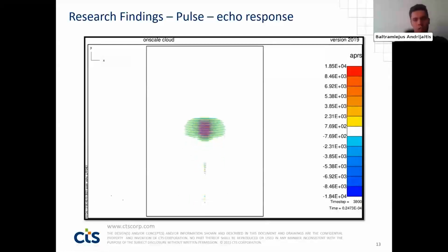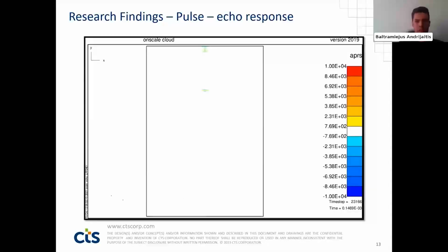This is the video pulse echo simulation. We can see high frequency 20 pulses that were excited in the ceramics, traveling in the water, hitting the mirror, and traveling back where the echo signal is read. So here, talking about what is important to perform a good pulse echo finite analysis. It is important to ensure that a high acoustic impedance material is used for the mirror. In this case, it was stainless steel. And another point, the distance between the sample and the mirror should be set exactly as in the real case. Otherwise, the signal would not represent the real case in general.